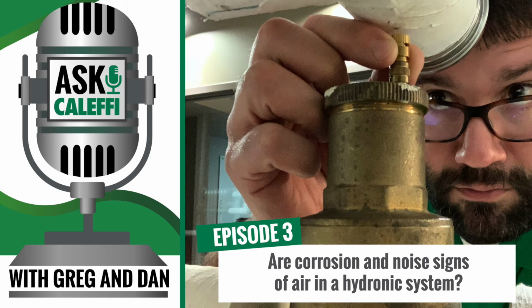So the hot side of the chiller, essentially. On a boiler, you put it on the supply line coming out of the boiler, where the water temperature is the hottest. With a chiller, you reverse that, and you have it on the inlet side coming into the chiller, where the water is the warmest. That's the most oxygenated water, after the cold is absorbed out of the chilled water. We're rated for use between 32 and 250 degrees Fahrenheit, so we cover either a chilled or hot water application.